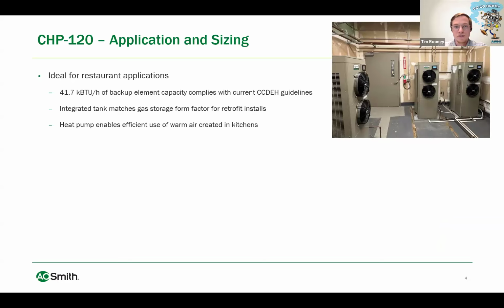So when it comes to applications, we've seen quite a bit of success in restaurant applications with this product. There's a few reasons for this. One of them is that with current CCDEH guidelines, which Amin did a great job explaining earlier today, most jurisdictions will only allow heat pumps and heat pump water heaters to be sized based on the input power. Because these have backup electric elements, those elements are allowed to be used in the sizing calculation, meaning that about half the capacity of the unit can be accounted for, where compared to true split systems, depending on the jurisdiction, they may not even allow this to be installed.